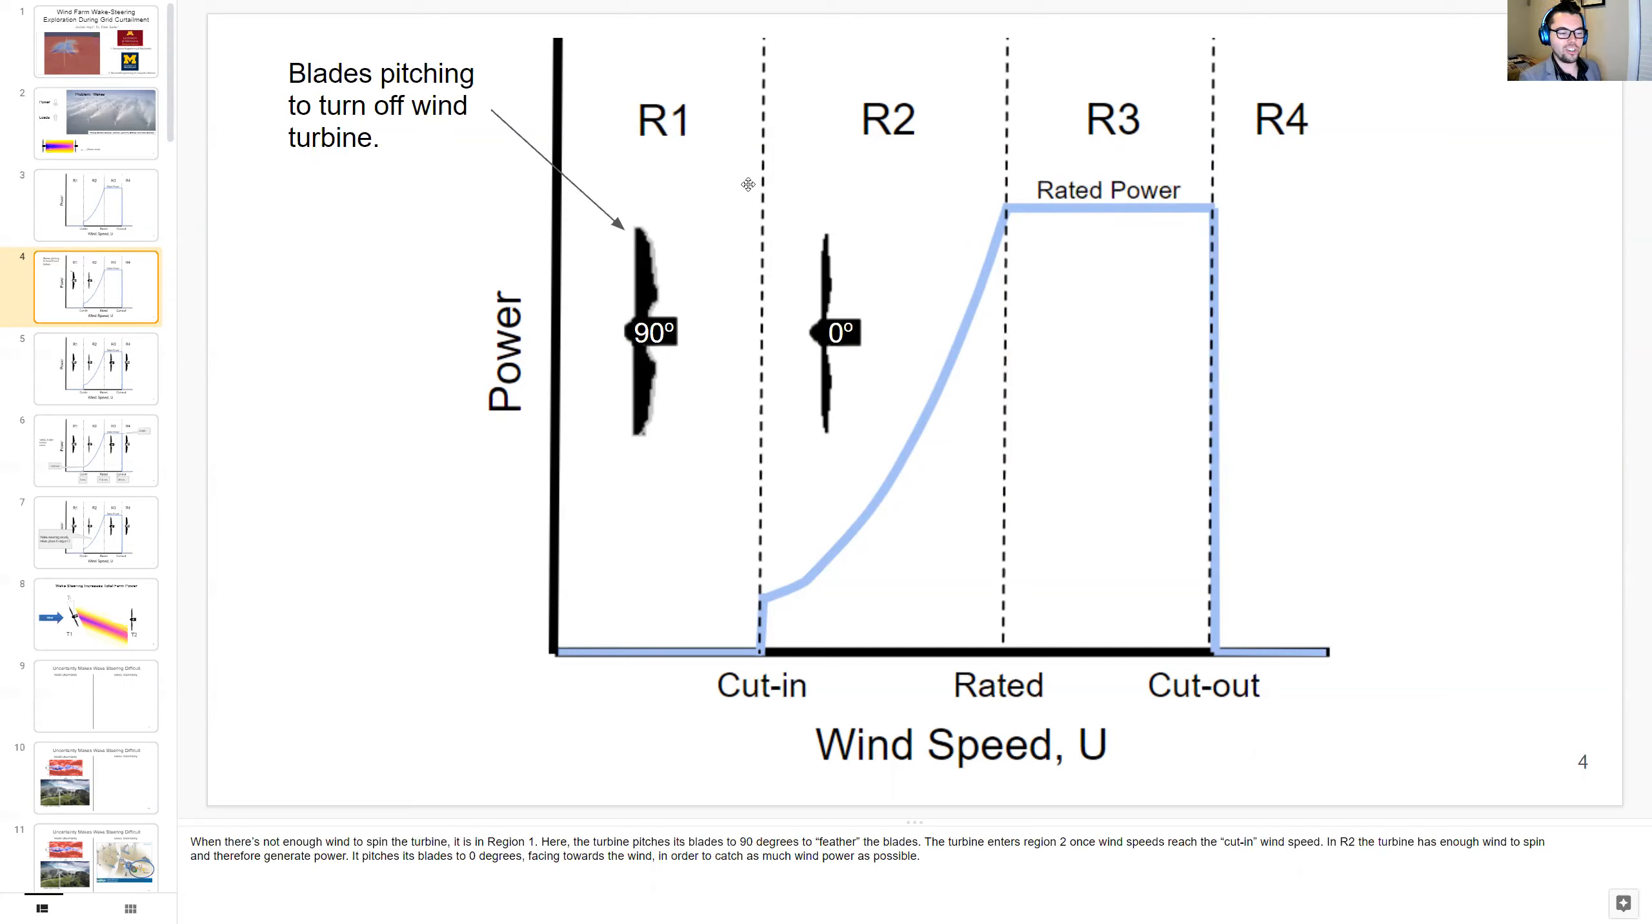The turbine enters region 2 once wind speed reaches the cut-in wind speed. In region 2, the turbine has enough wind to spin and therefore generates power. It pitches its blades to 0 degrees facing towards the wind in order to catch as much wind power as possible.